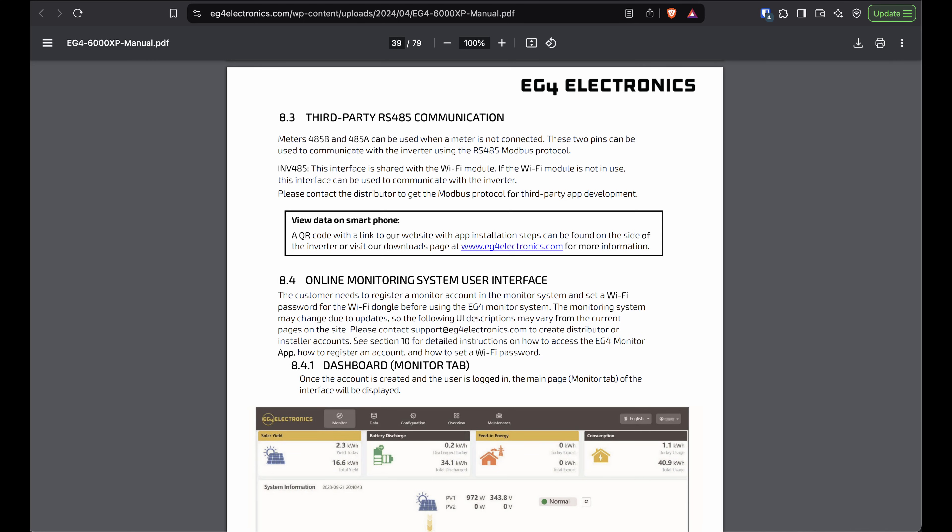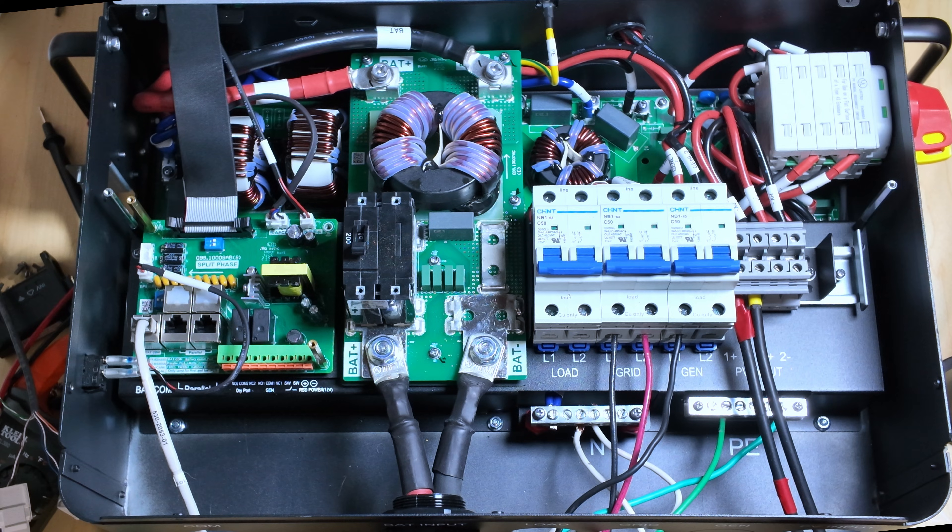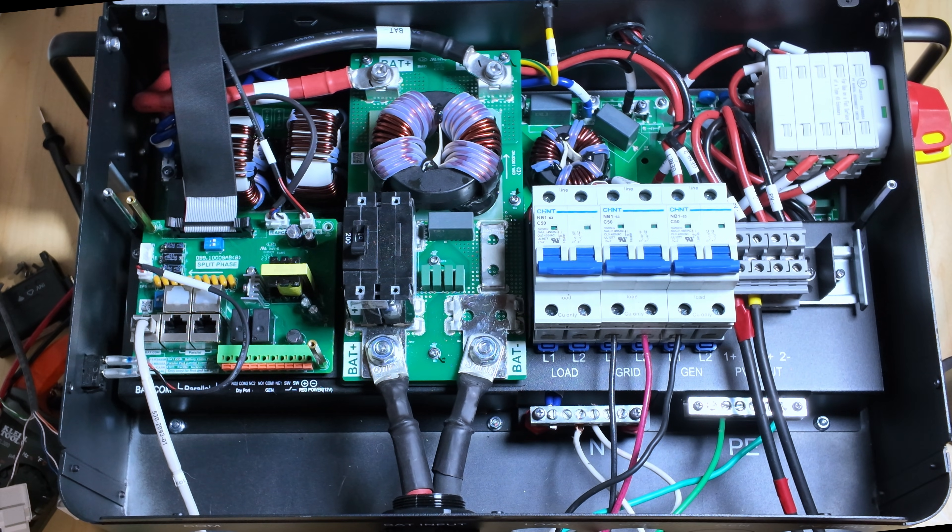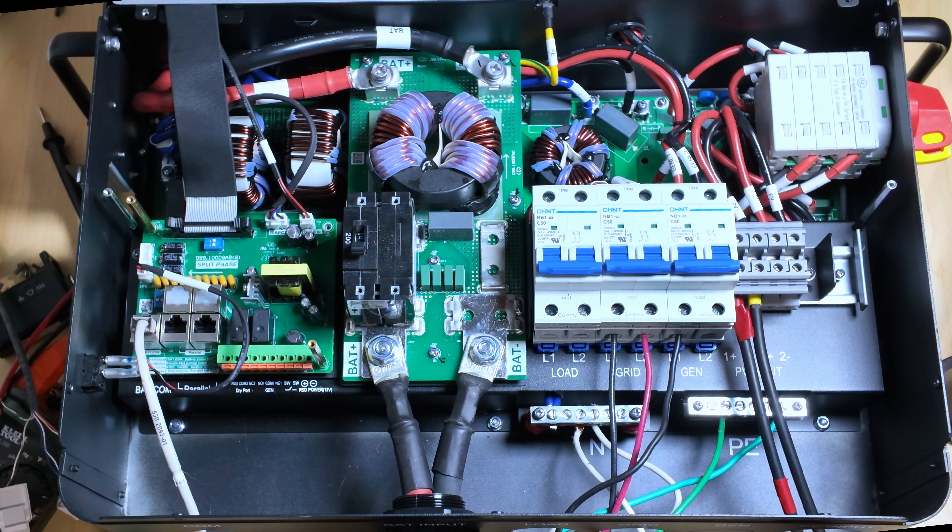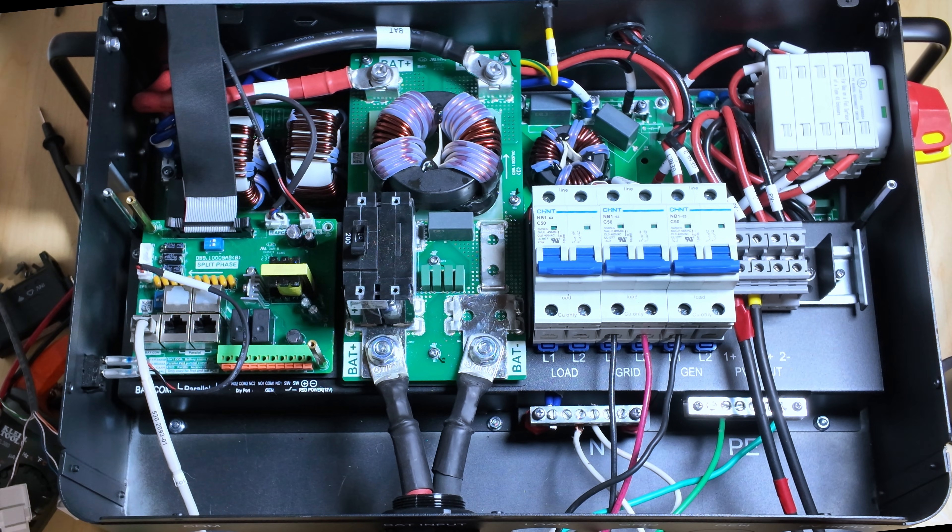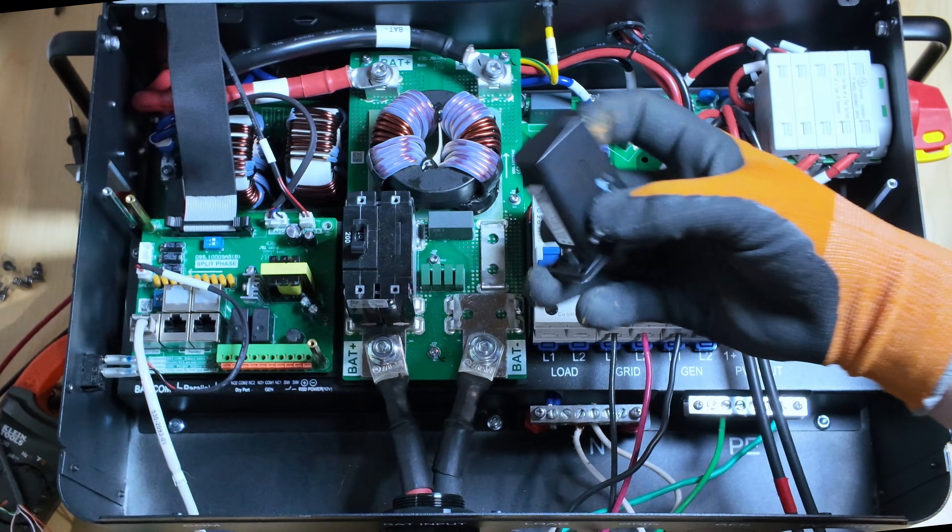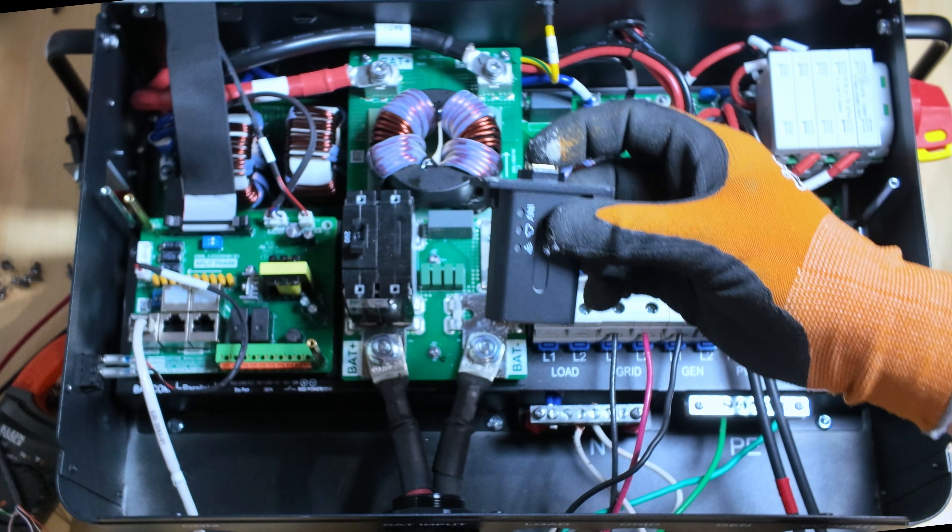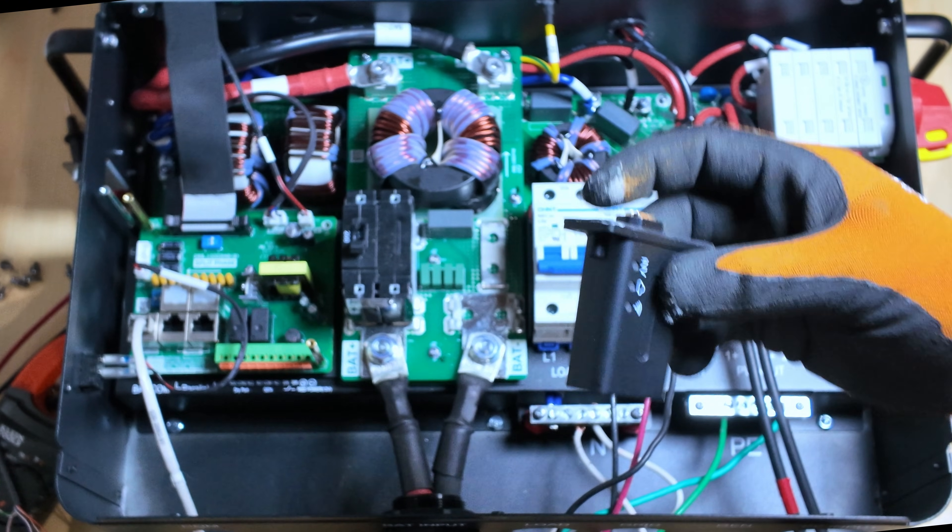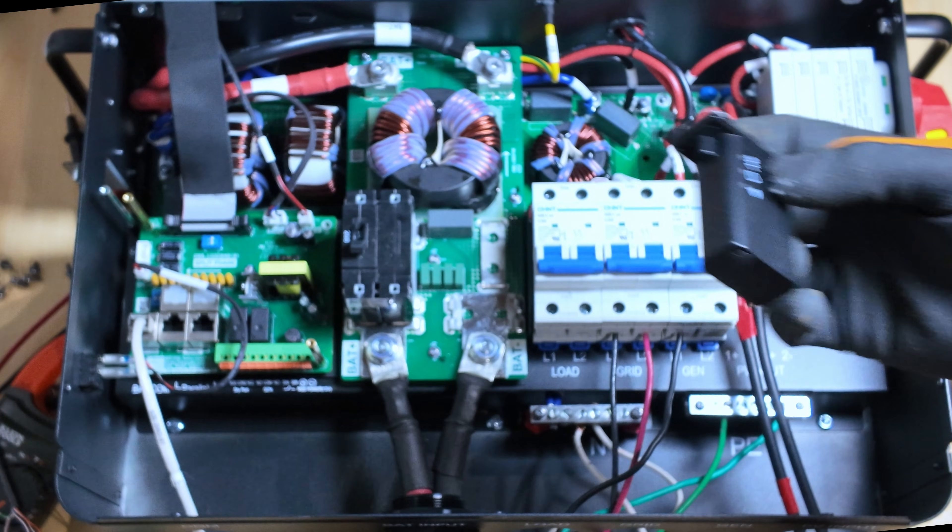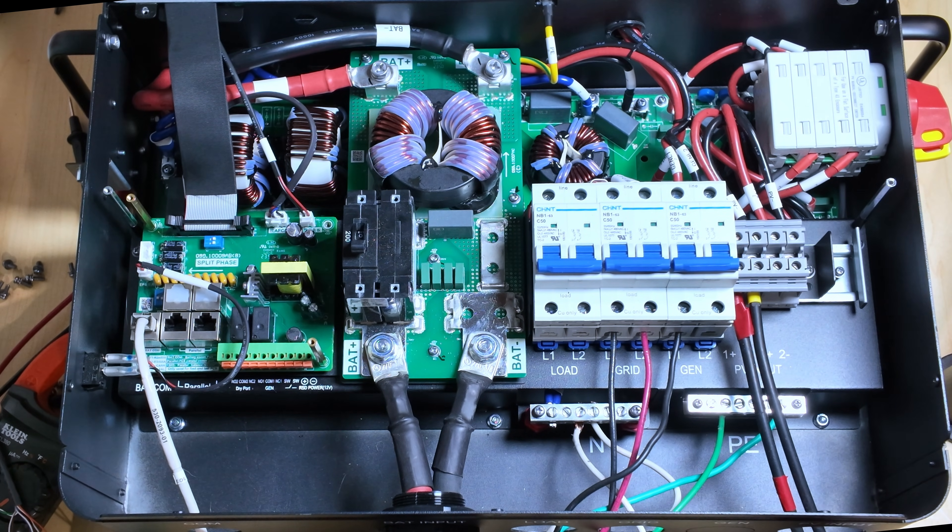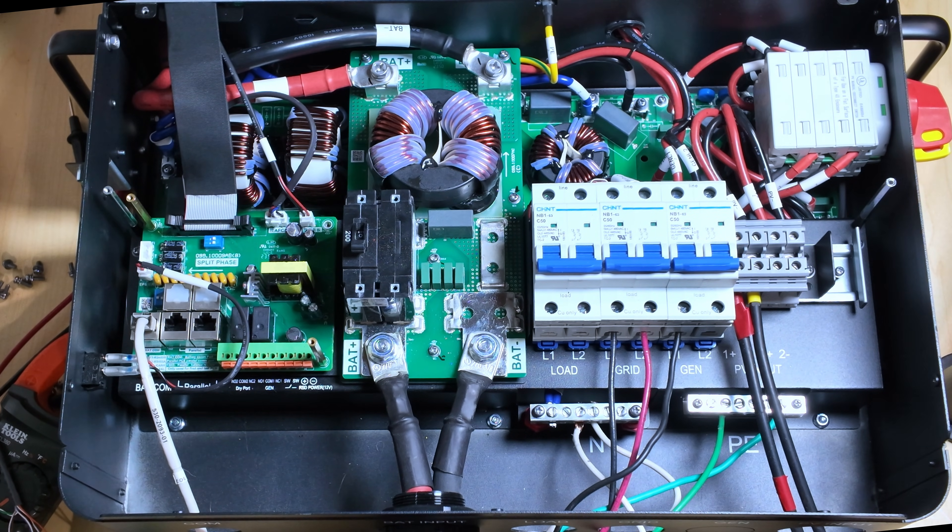If you look at the manual in section 8.2, at least in the paper copy that I have, it says that there is an RS-485 connection for third-party communications. So I was trying to figure out exactly where this is. And in that section, it says that it's tied to the wireless dongle. So you can't use both the wireless dongle and the hardwired RS-485 at the same time.